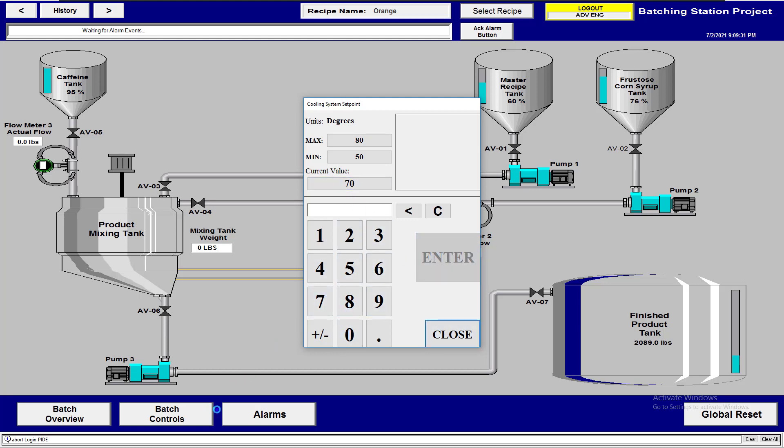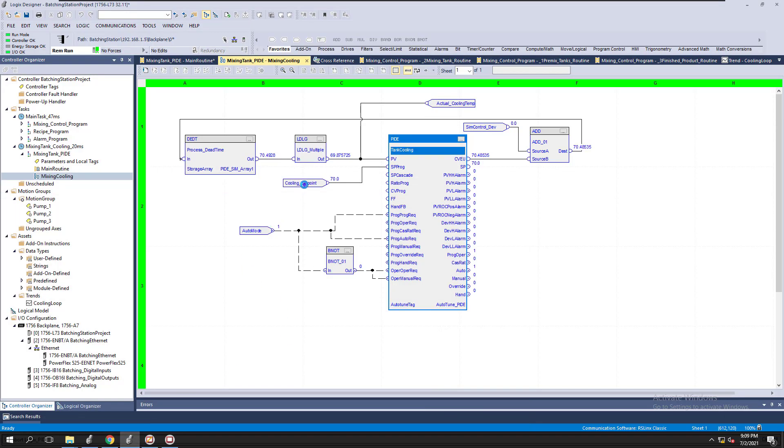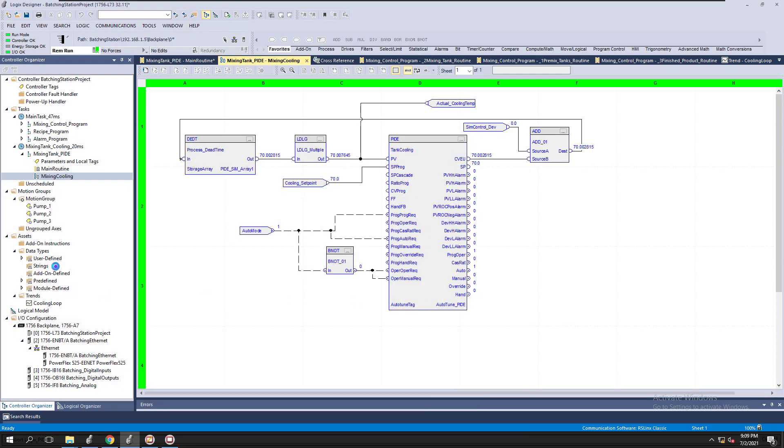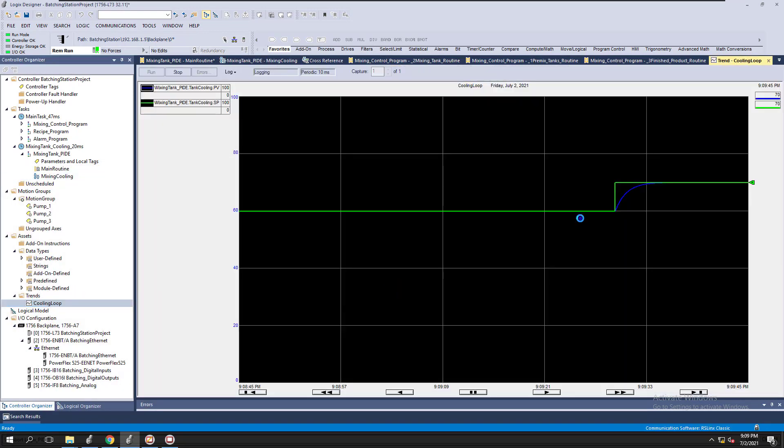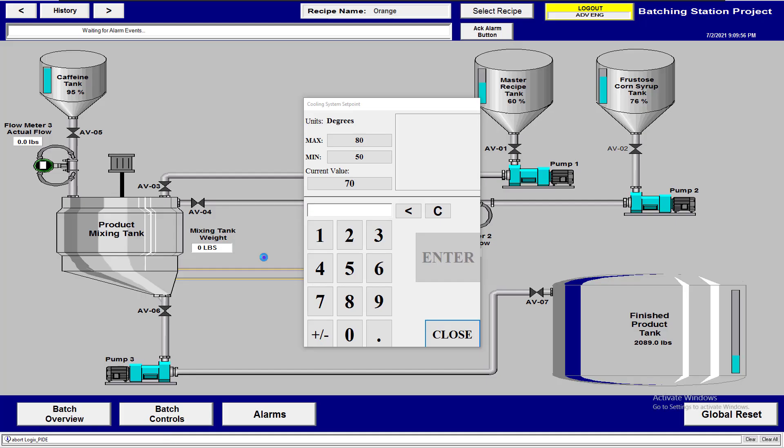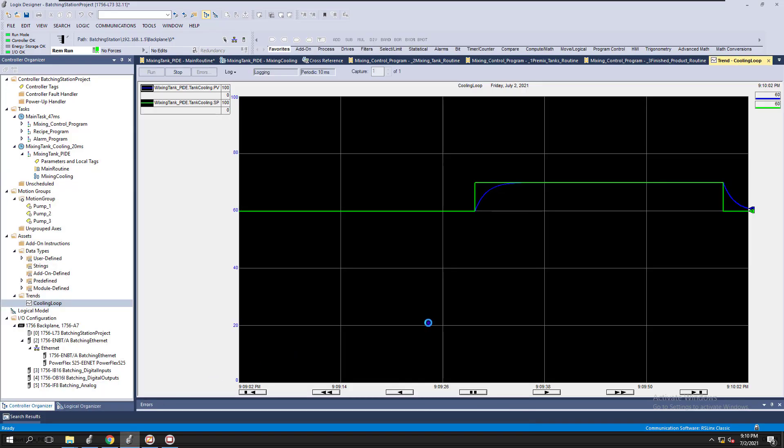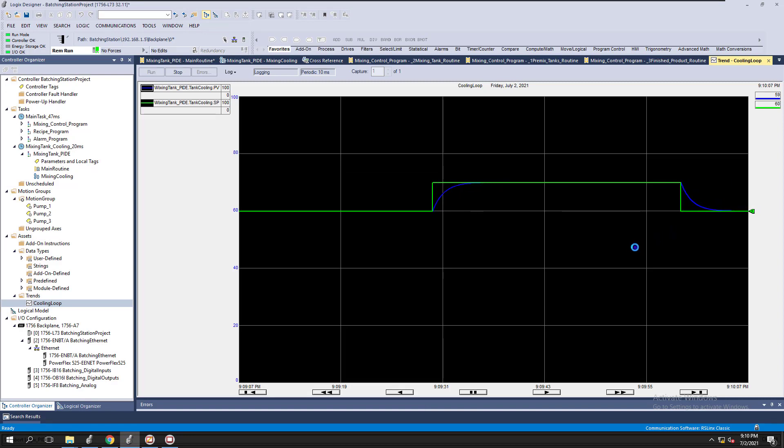And so if we go into our code, go into our code and now it's changed our set point to 70 degrees, which is automatically working because we have, so you could actually see that off the trend it's automatically working because we've actually changed the set point and a nice little curve there, to be honest with you from the tuning. We just did nice little curve work perfectly. We changed the set point. Let's do that again. So let's go back to 60 and let's come back into here and change this and watch this one more time. So that that's a nice little curve we got from the auto tune. So that's a really good feature.